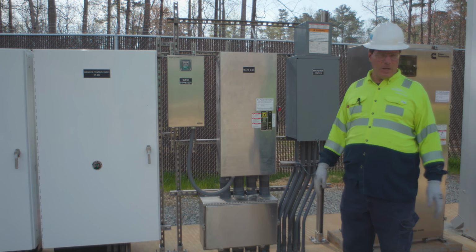Then you have a power okay indication light, which must be burned out, by the way, because I can tell there's power, but that light's not on. It should be on. And then you've got 3 elapsed time meters, 1 for each motor, all of them showing about 7 hours apiece. Then you have the hand-off-auto operation for each pump. Unlike other places, these will start running the second you put them in hand, as long as the PLC is not in operation. If the PLC is in operation, then it may prevent you from running these in hand.